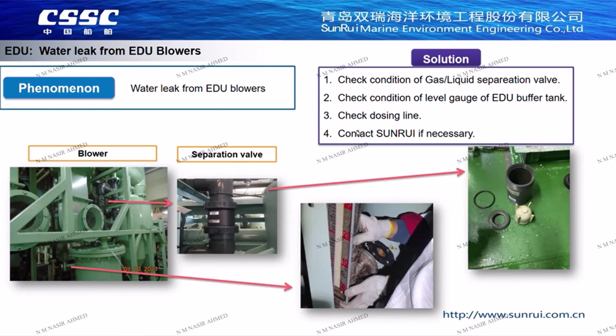In this position, it needs to be opened for cleaning to see if the floater is stuck or has lost efficacy. Secondly, check the liquid level meter of EDU buffer tank. After a long time, salt might accumulate at this position. Of course, the liquid level gauge could not display the actual liquid level, misleading the system and causing the occurrence of water leakage.